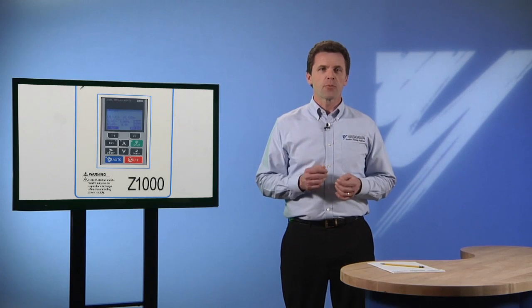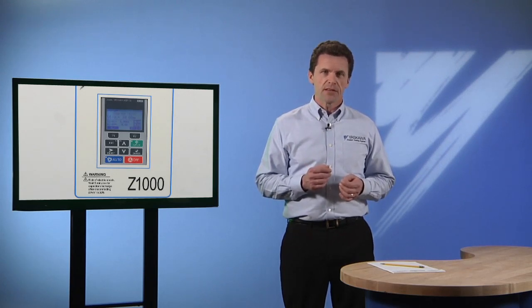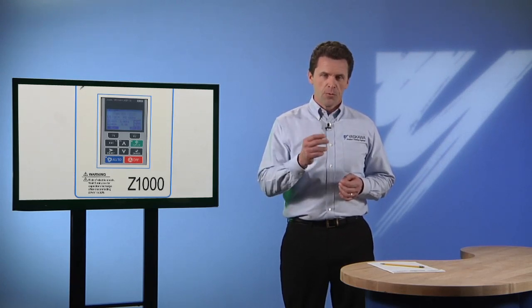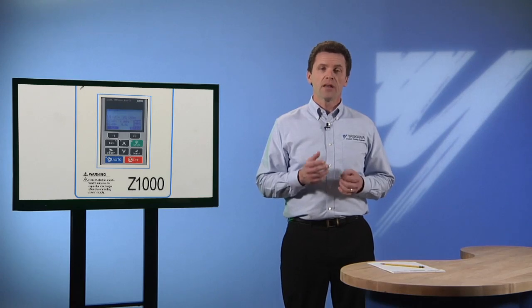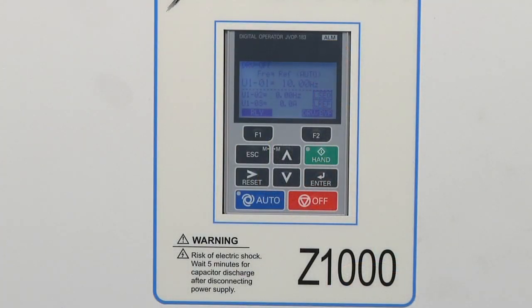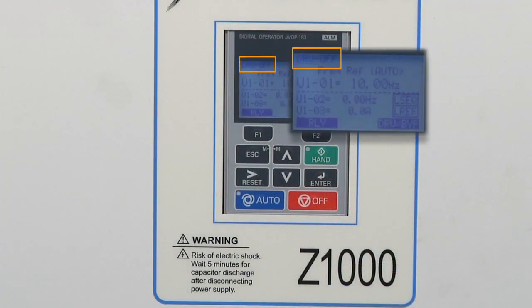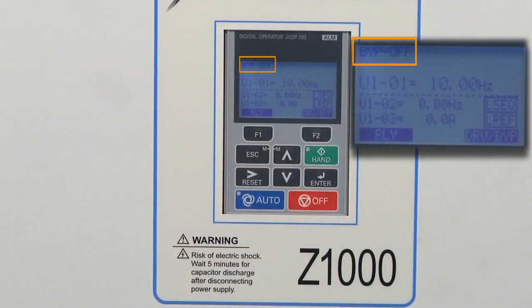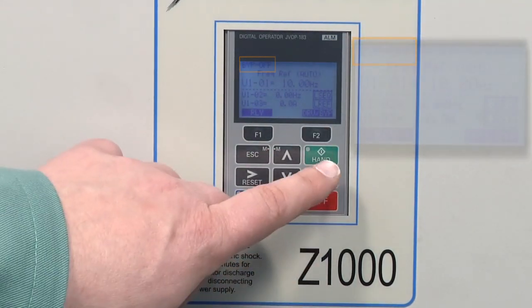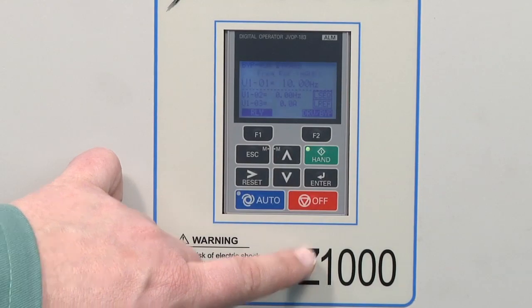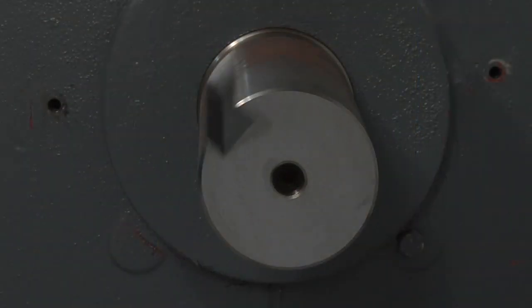Once 60 Hz operation has been achieved, press the off key to stop the motor. We can begin our testing of the operation while in bypass mode by changing from drive to bypass, and this is done by pressing the F2 key. We can then bump the motor by pressing hand, then off fairly quickly, one right after the other. This will allow you to check the motor rotation.